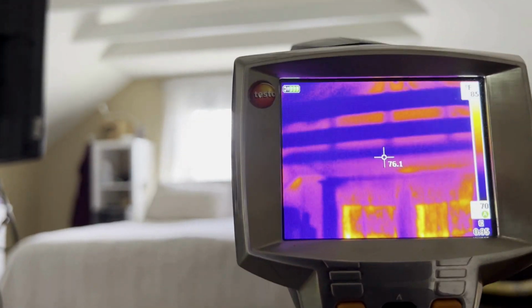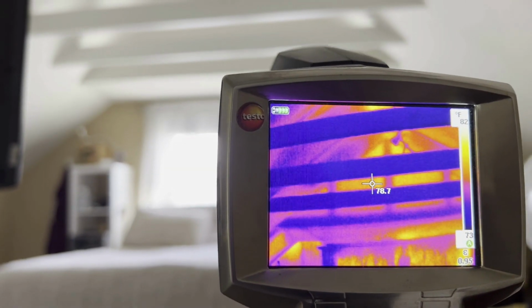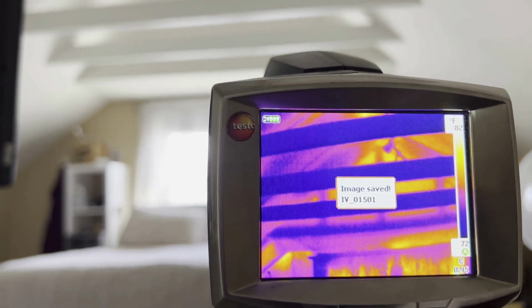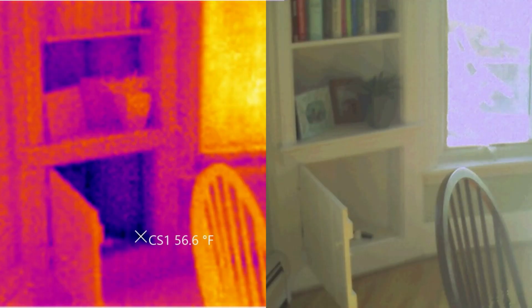Usually, the places that you have the biggest problems where ducts get disconnected are in crawl spaces and attics, places that people do sometimes traverse, or where different things are going on. They're subjected to a little bit more of the elements, so the tape that's holding things together may fail, or possibly when the work was being done, because it was in extreme conditions, it wasn't done exactly right, or it could be where it was done to the best of their ability, but because of weather changes, things flex and change, and things get disconnected.